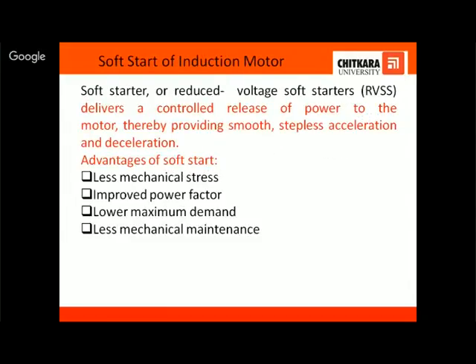So we can recommend the soft start of induction motors. Basically these are reduced voltage soft starters. They deliver a controlled release of power to the motor, so there is a smooth, stepless acceleration and deceleration of the motor. The advantages of soft start are less mechanical stress, better power factor, and lower maximum demand, because there won't be inrush current at the starting.